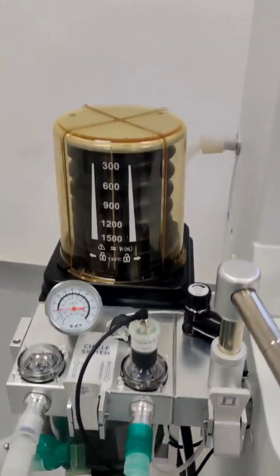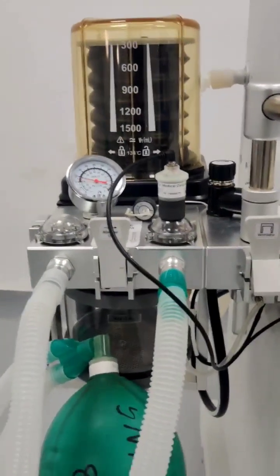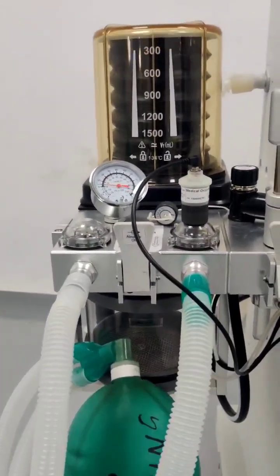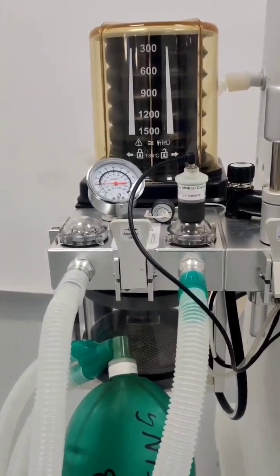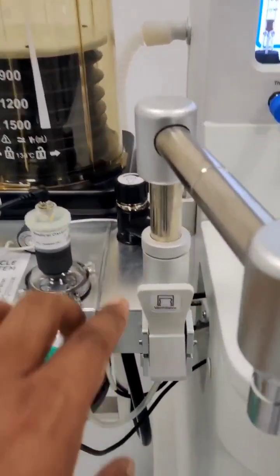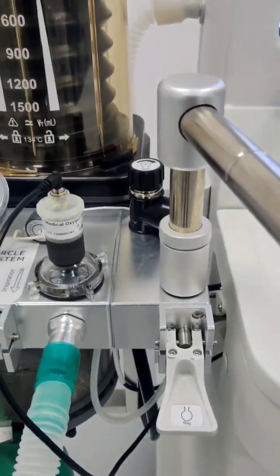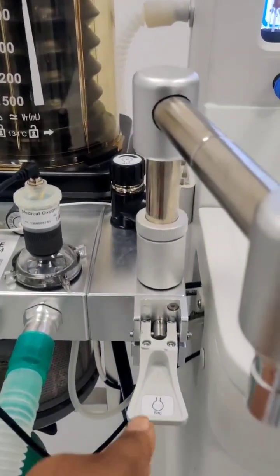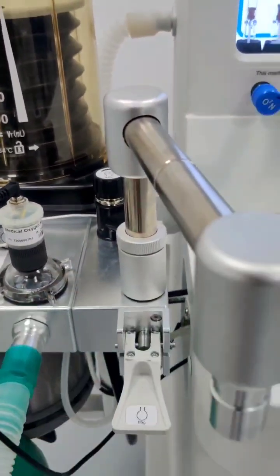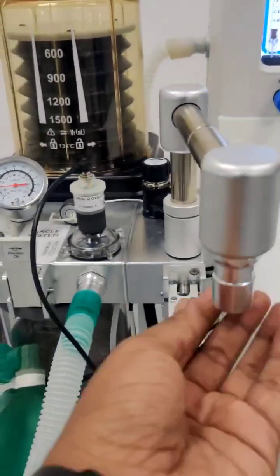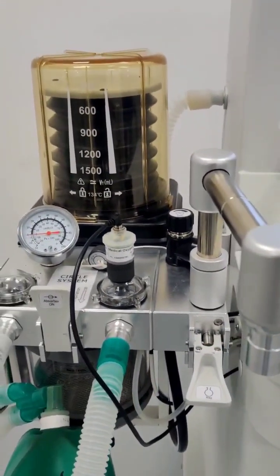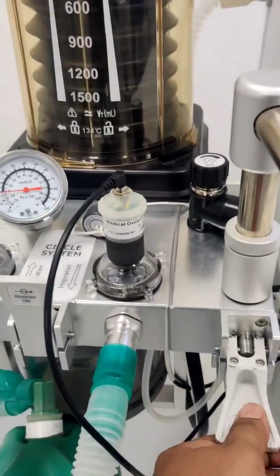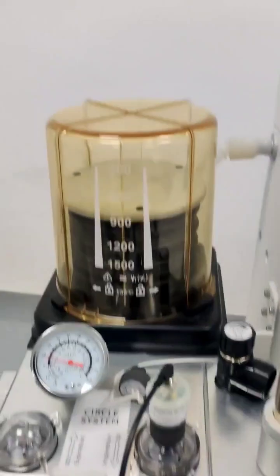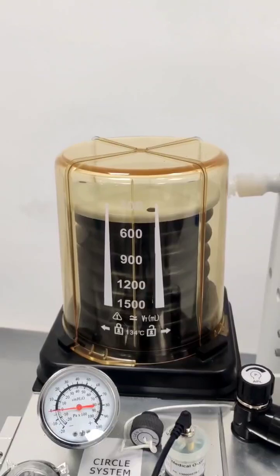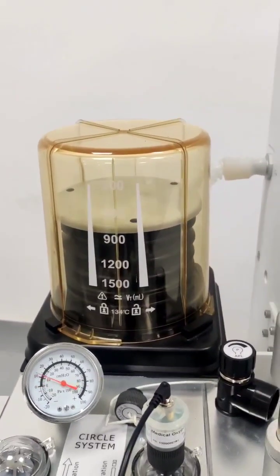So this is the circle absorber system, which has a single canister configuration. This canister will hold around 1 kg of soda lime. We are giving a bag to vent switch for the changeover from manual to automatic ventilation. During manual ventilation you can put the breathing bag over here for manual ventilation of the patient, and as soon as you put it to the automatic ventilation mode, the bellows will get activated and all the gases will be going to the patient with the help of the bellows.